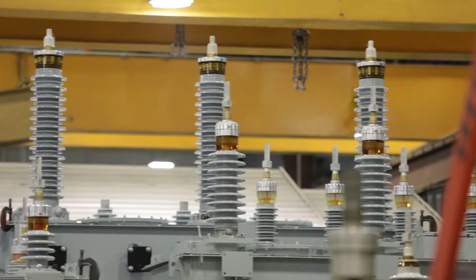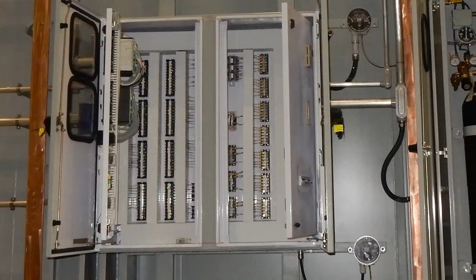The core and windings are contained in a rectangular mechanical frame called the tank. Other parts include bushings, which connect LPTs to transmission lines, as well as tap changers, power cable connectors, gas-operated relays, thermometers, relief devices, dehydrating breathers, oil level indicators, and other controls. Here's what it takes to manufacture an LPT.